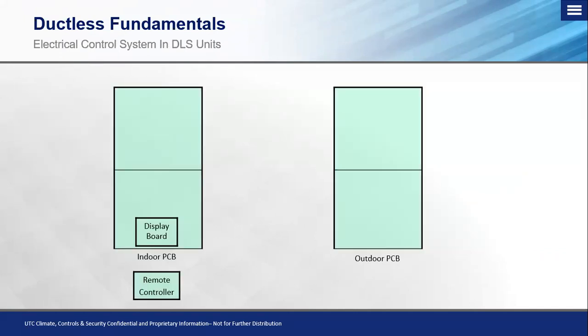So as a general rule, if we take just a generalized overview of what we've talked about so far, we have a basic makeup of a ductless system. We have an outdoor PCB and an indoor PCB. We have our T1 and T2 sensors, which we know as return air, and indoor coil temperature sensor. We also have our TS, which is the set point by the controller, whether that be wired or wireless. We have our fan speed, which reports back to the indoor PCB, and that's looked through as RPM, or revolutions per minute, just like we would look at in a car with an RPM or a tach meter.